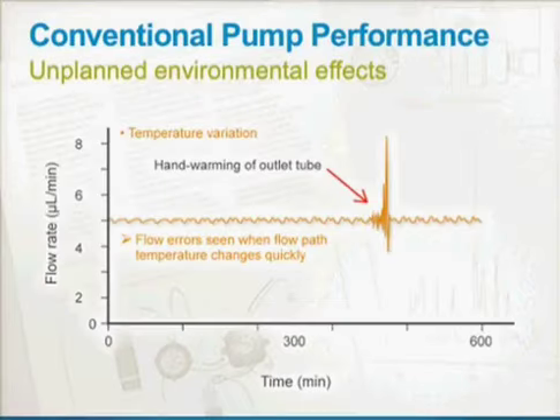And that's what your flow sensor devices helped us appreciate. Remember, a mass spectrometer is a concentration-sensitive detector, so a lot of times you're not going to see the impact of a flow rate change unless you start to do creative things in the flow path like we're doing. And so even just a simple action of putting your hand over, not touching, the fused silica tubes connecting to the mass spectrometer, you could see that change the flow rate. From the temperature. From the temperature, yeah.